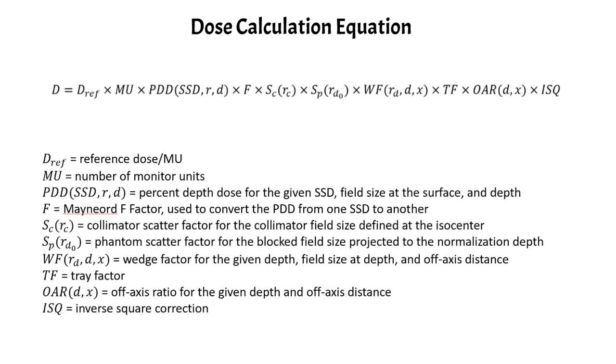You have the collimator scatter factor here for the collimator defined field size at the isocenter. You have the phantom scatter factor for the block field size projected to the normalization depth. You have your wedge factor, tray factor, you might need an off-axis ratio, and you also have your inverse square correction.